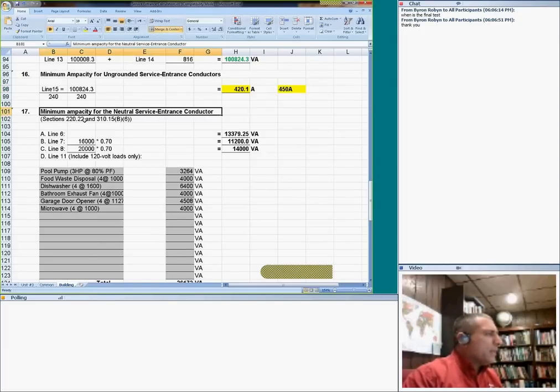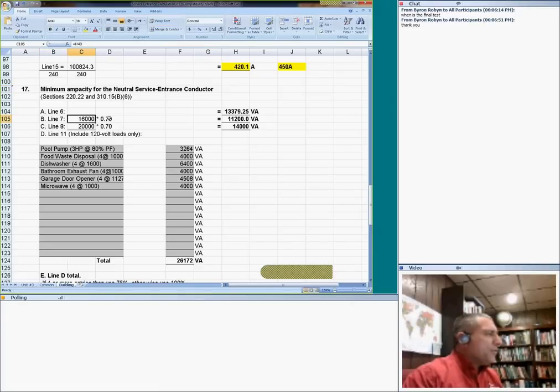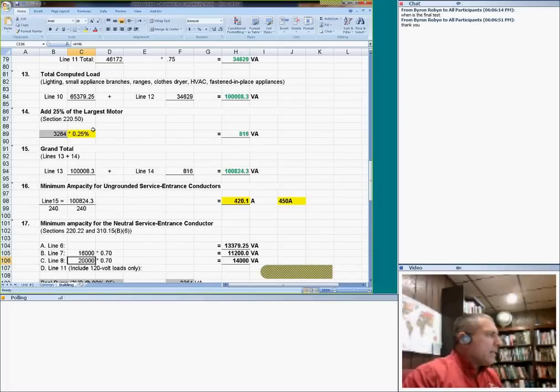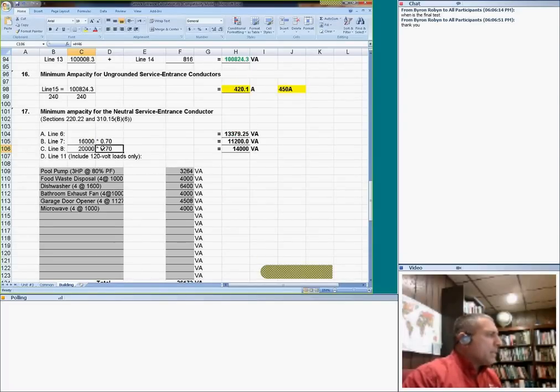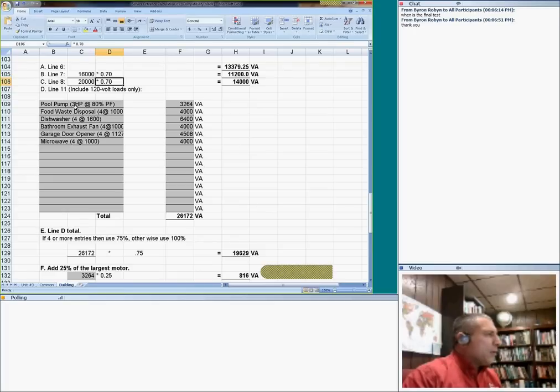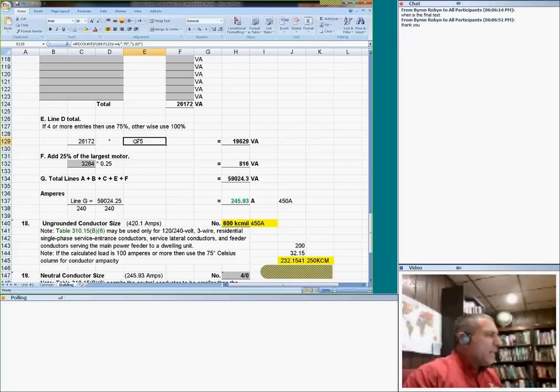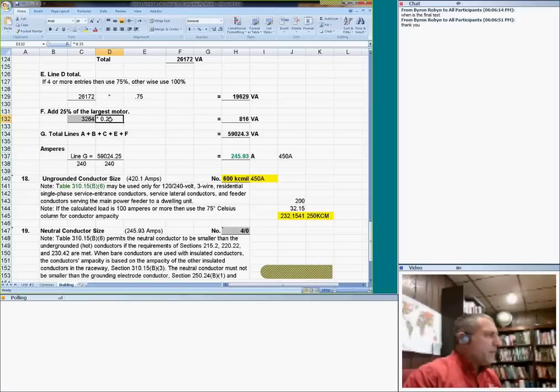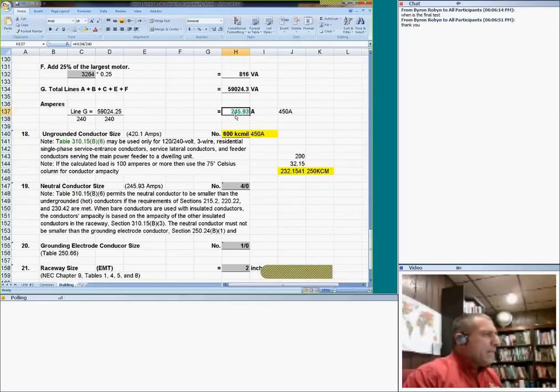Can you guys see how you get the neutral here? Then you take the ranges, cut them by 70%, and get the ranges and the dryers. You cut them by 70%, and you take only the 120 loads, because 240 would not be seen by the neutral. 120. And cut them by 0.75, exactly like we did for the feeder. Increase 25% on them. And my service neutral size, my friend, would be 245 amps for the neutral.